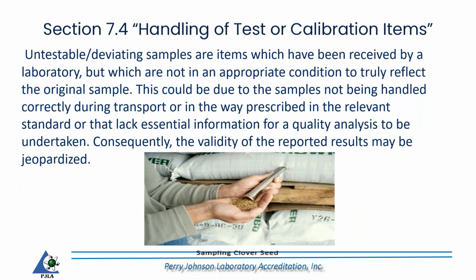The sample, folks: other than the environmental conditions that need to be met, perhaps you received some untestable or deviating samples which have gotten to the lab. And these would be samples that the customer provided you, which would be as received. So in other words, you didn't go out and take the sample. You're going to test it as received by the customer. However, deviations could be due to the sample not being handled correctly during transport or in the way prescribed in the relevant standard, or the lack of essential information for a quality analysis to be undertaken. Consequently, the validity of the reported results may be in jeopardy.